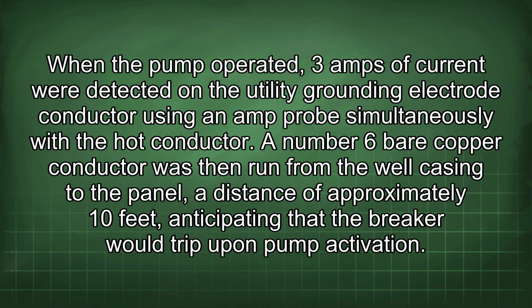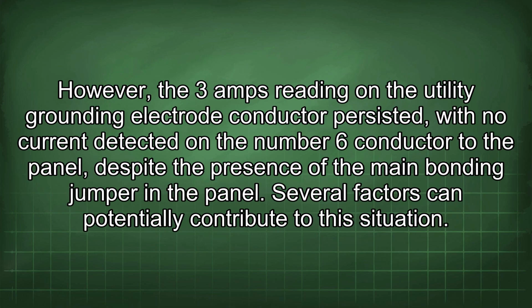When the pump operated, 3 amps of current were detected on the utility grounding electrode conductor using an amp probe simultaneously with the hot conductor. A number 6 bare copper conductor was then run from the well casing to the panel, a distance of approximately 10 feet, anticipating that the breaker would trip upon pump activation. However, the 3 amps reading on the utility grounding electrode conductor persisted, with no current detected on the number 6 conductor to the panel, despite the presence of the main bonding jumper in the panel.